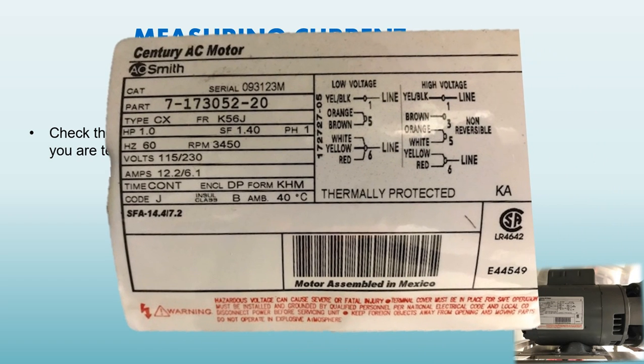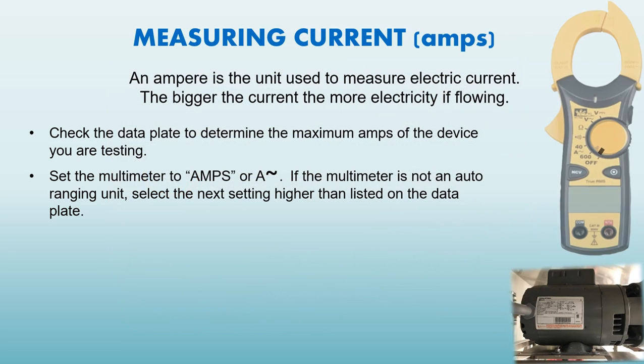Measuring current. An ampere is a unit used to measure electric current. The bigger the current, the more electricity is flowing. Check the data plate to determine the maximum amps of the device you are testing. On all machines or motors, there should be a data plate that will show you what the amps should be. On this particular motor, it can be wired for low voltage or high voltage. This particular motor runs low voltage, and it would max out at 12.2 amps.